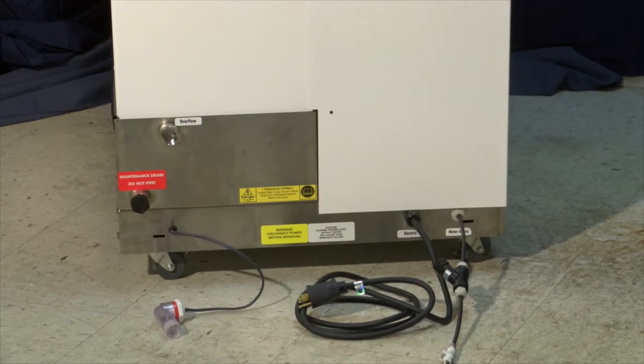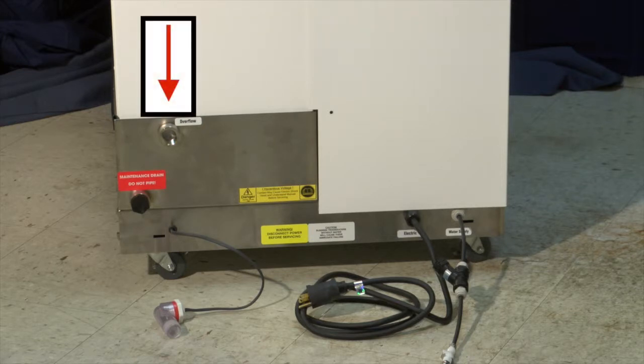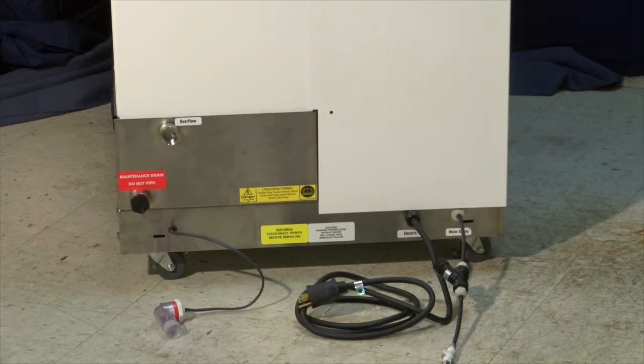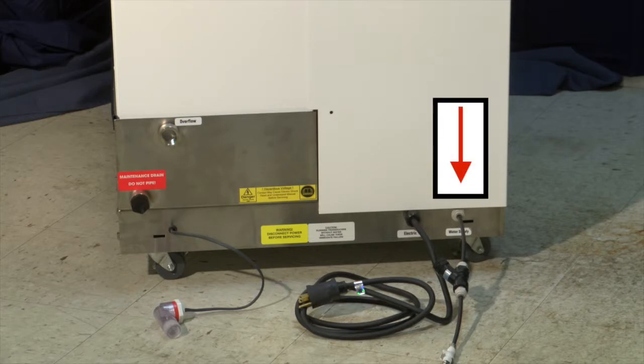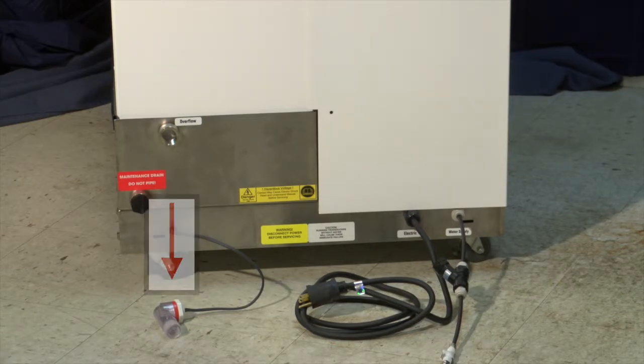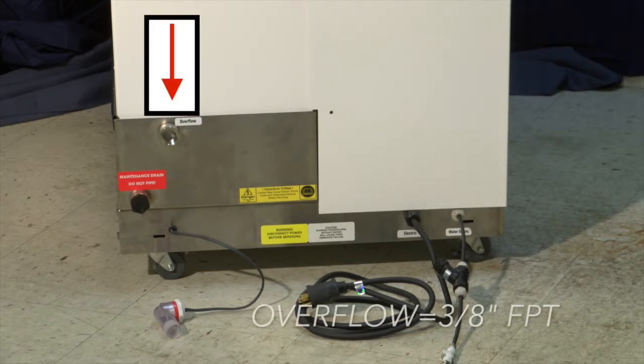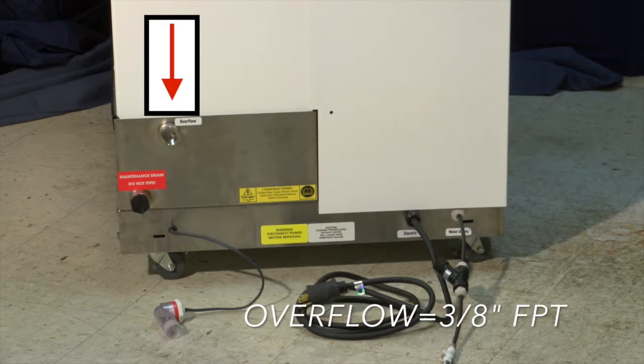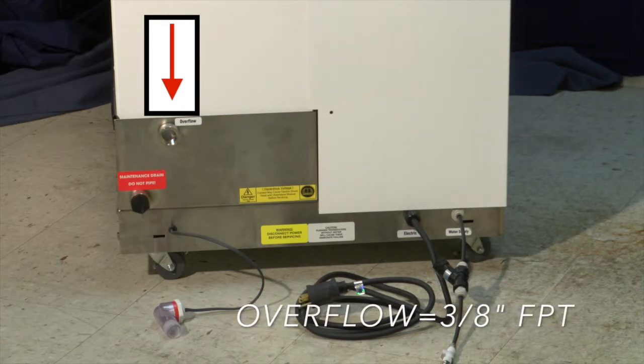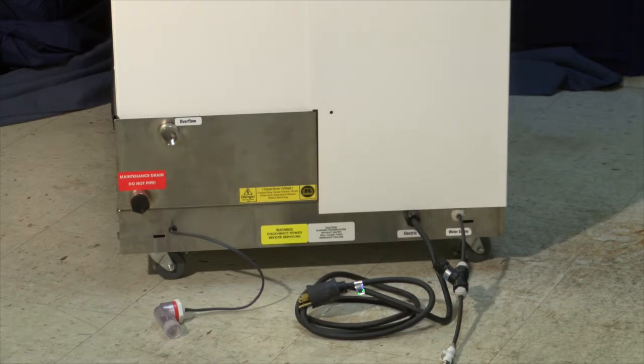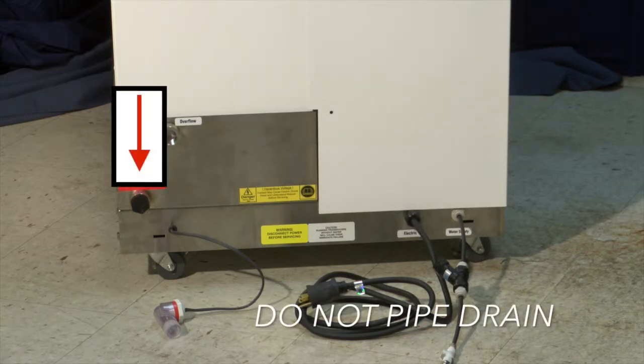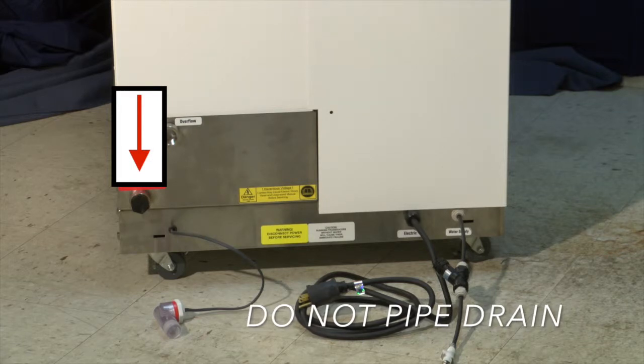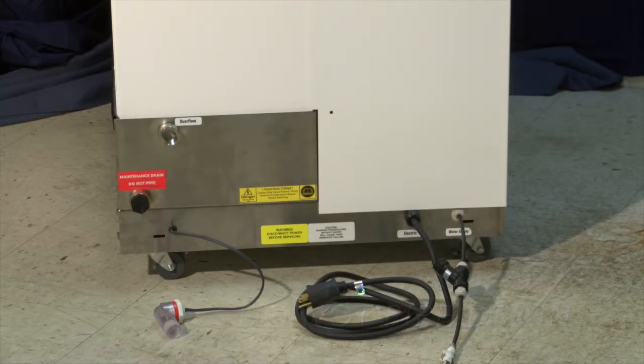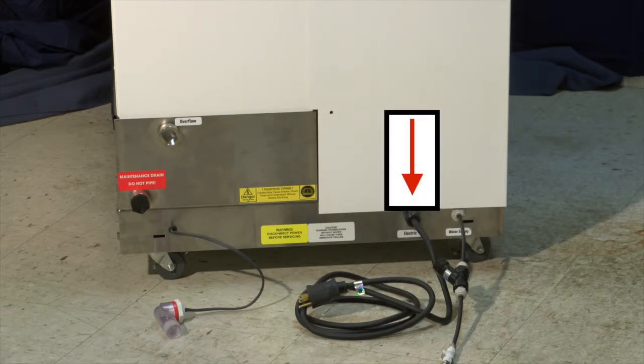On the side of the Mist-Free Series humidifier, you will see overflow, drain, electric, water supply, and the optional water guard sensor. Let's look at them one at a time. The overflow is a 3/8 female pipe connection used to direct an overflow in the humidifier's water pan to drain. The drain should not be piped, but you may add a manual ball valve to empty the water pan for maintenance. The electric connection is a standard 120 VAC plug.